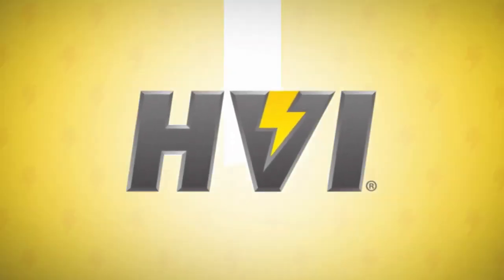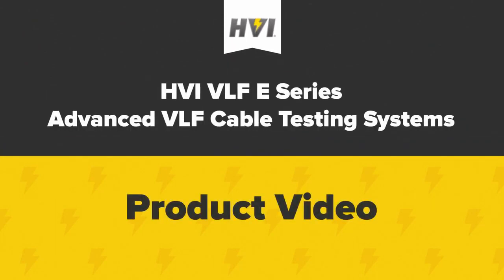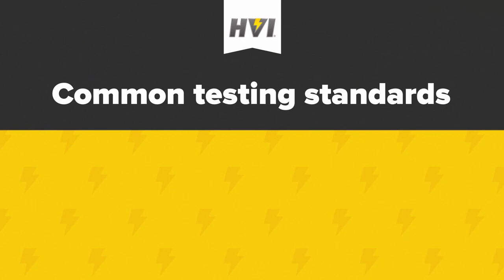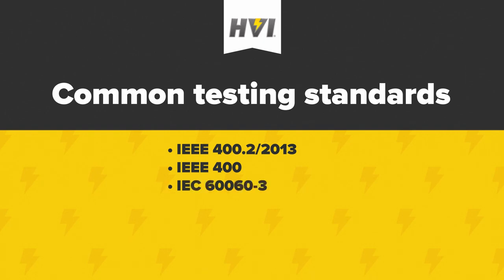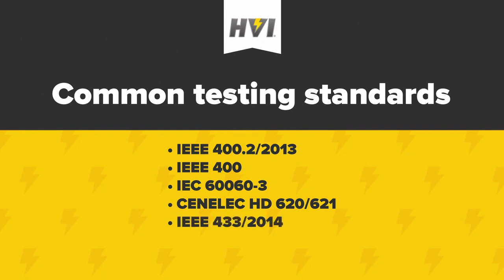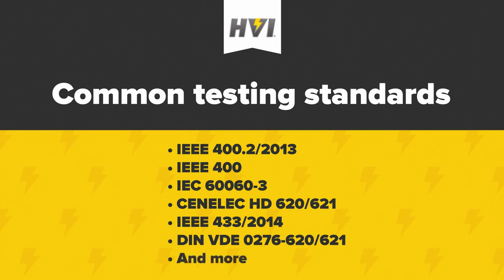HVI's VLF E-Series are advanced VLF, or very low-frequency, AC high pots used for the testing of high-voltage cables in motors or generators. Common testing standards that the VLF E-Series support include IEEE 400.2 2013, IEEE 400, IEC 60060-3, Cenelec HD 620, 621, IEEE 433 2014 for motors or generators, and many other local standards.